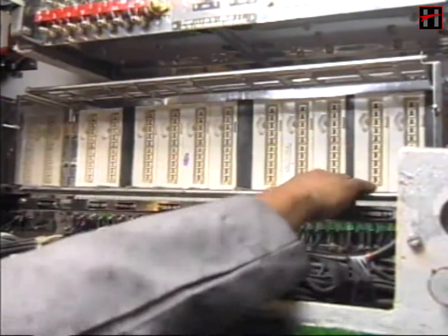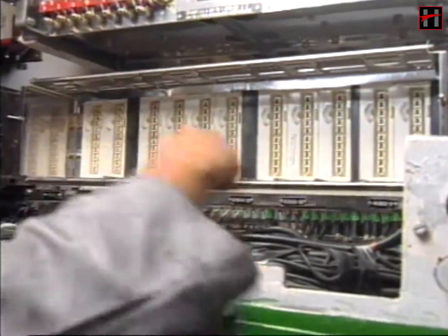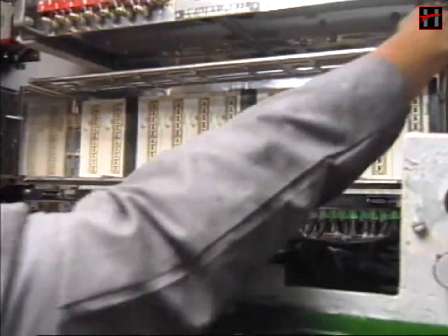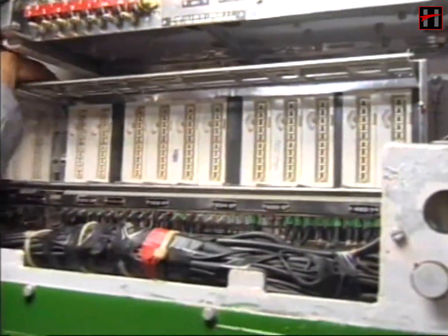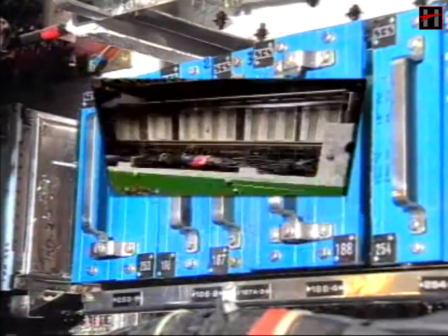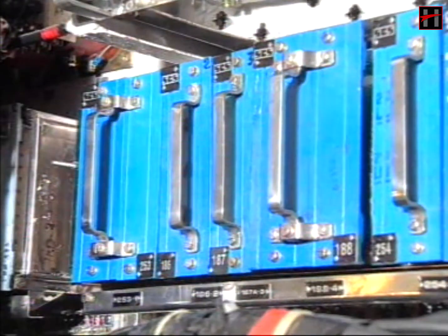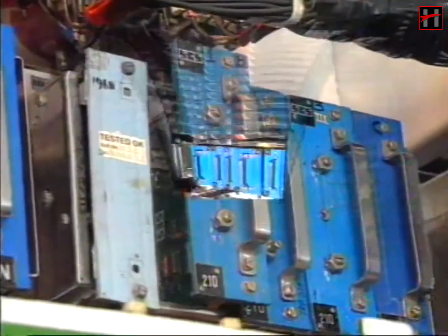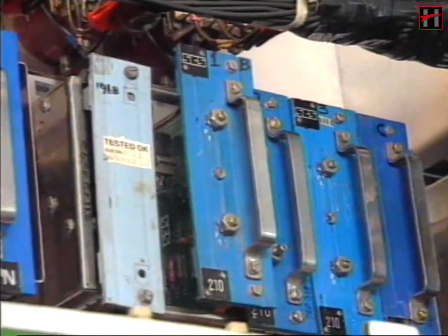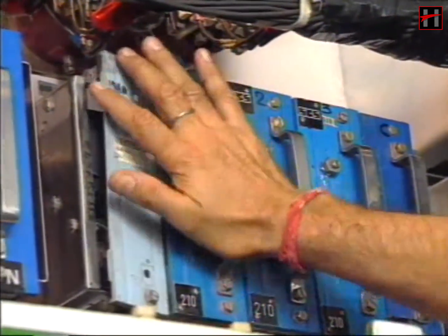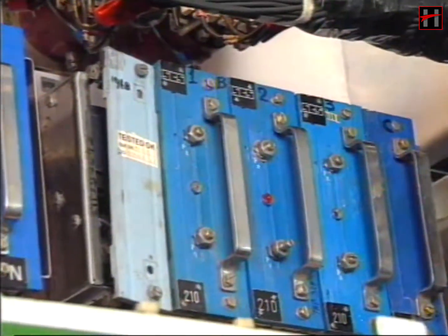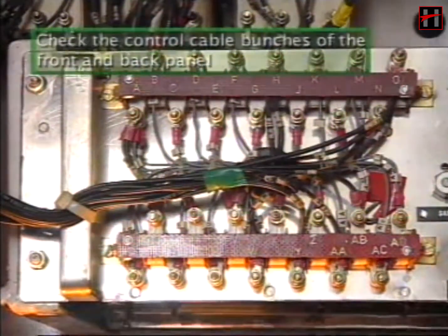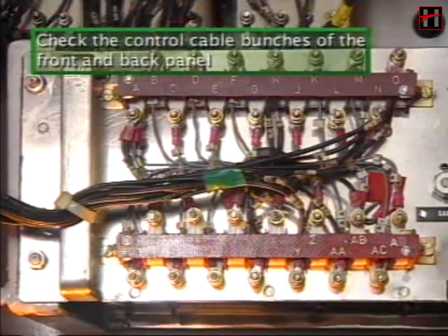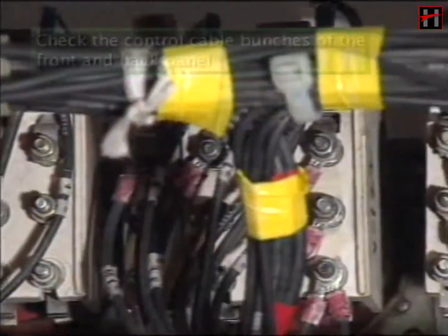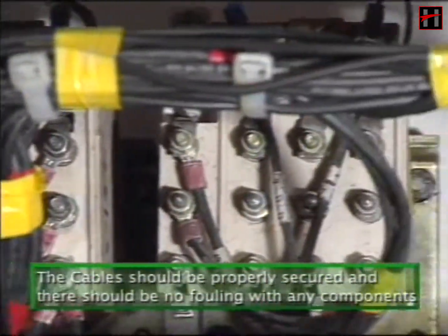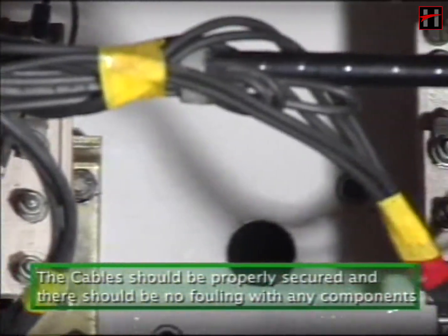Check the fitment of the control panel. Check and ensure that the cards of the excitation panel, VRP and TRP are properly fitted in their sockets. Check the control cable bunches of the front and back panel. The cables should be properly secured and there should be no fouling with any component.